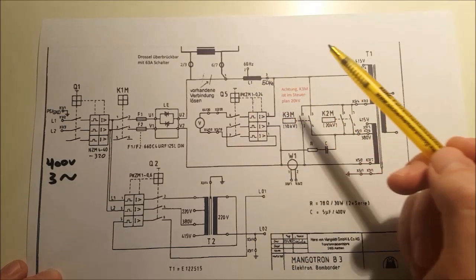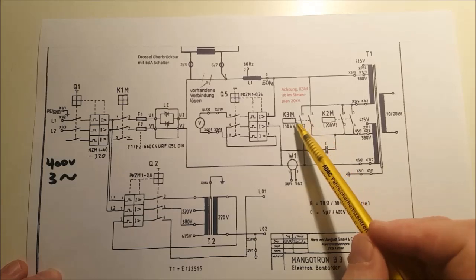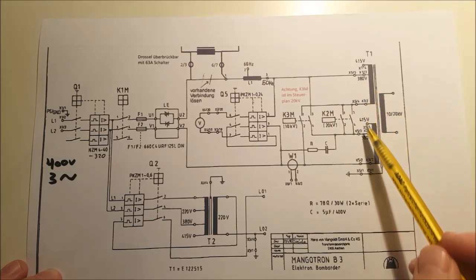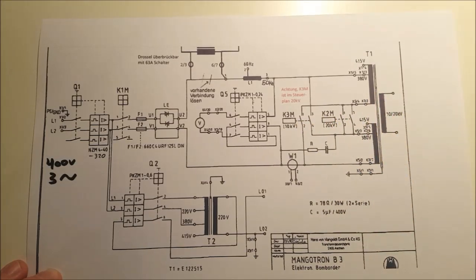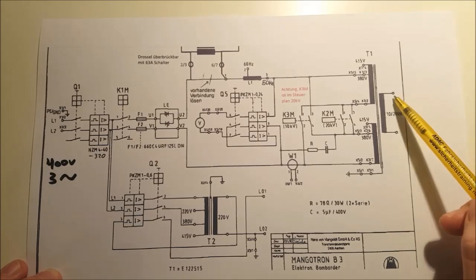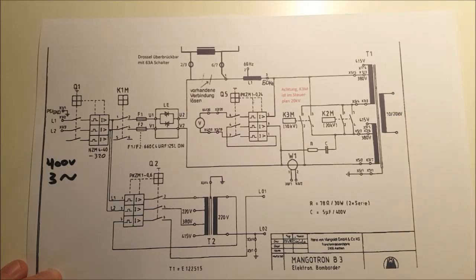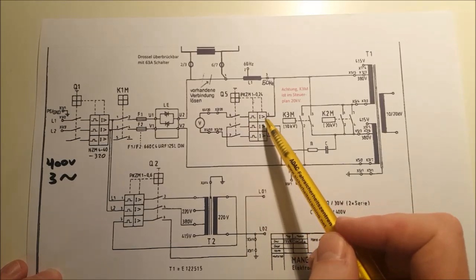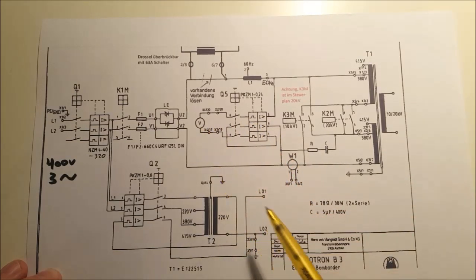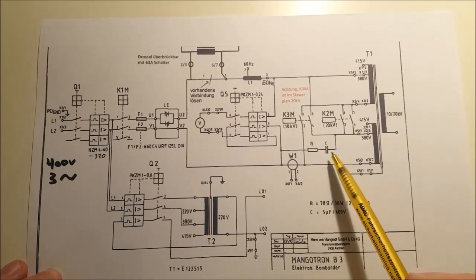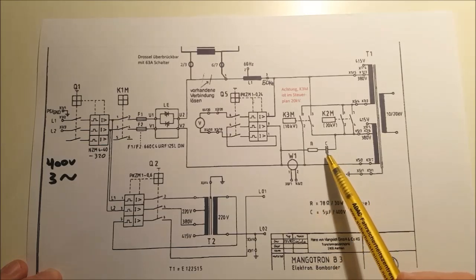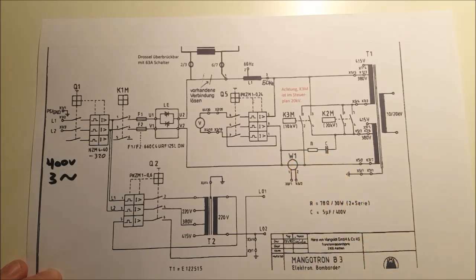Another smaller choke coil, and then these 2 contactors switch the transformer primaries to either the 10 kV or 20 kV mode. The transformer output, high voltage output, is here. Here's another circuit breaker protecting this voltmeter, current sensor down here, and I must admit I'm not sure what these resistor and capacitor here are doing. And then down here there's another circuit breaker protecting this control voltage transformer that makes 220 volt output for all the contactors.